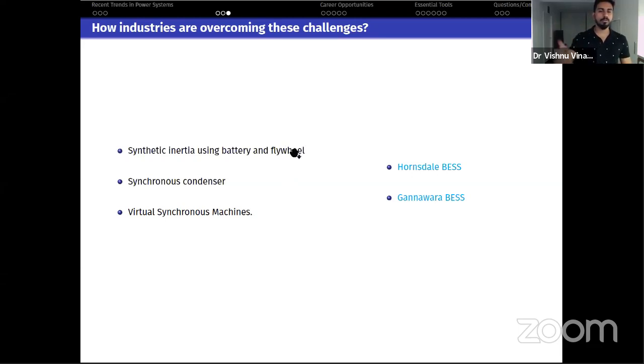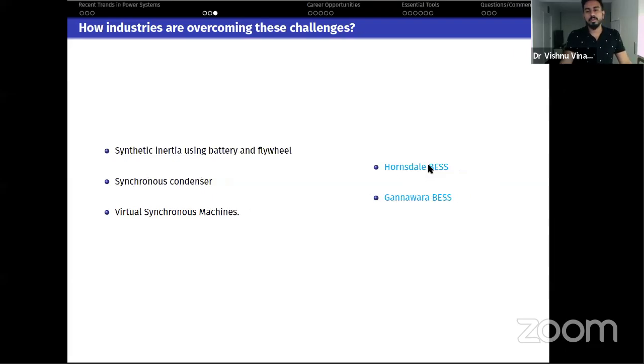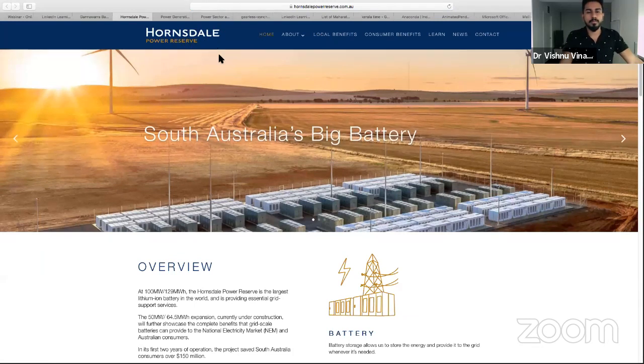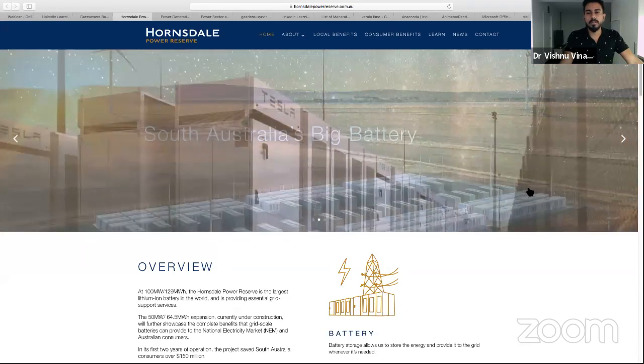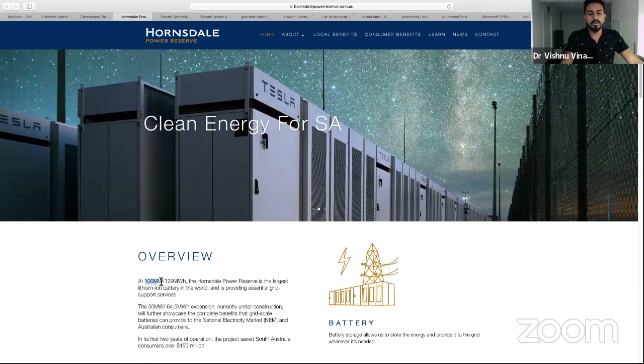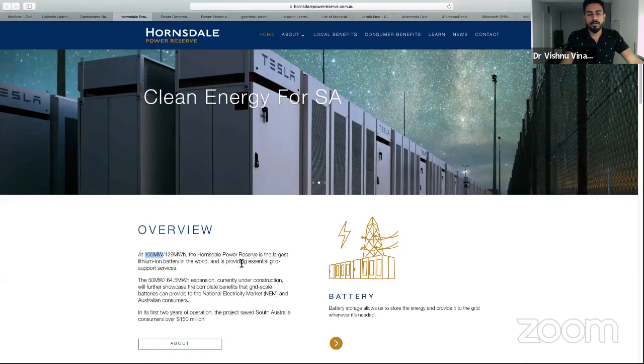Similarly, flywheels are huge rotating masses, so they store inertia and work in a similar fashion. Utility scale batteries are being installed in many power system networks, and I have provided an example here. This particular project is called the Hornsdale Battery Energy Storage System, in South Australia. You can see that these blocks are all batteries made by Tesla. These are Tesla battery packs, and the capacity of this battery is 100 megawatts, and it is used specifically for providing essential grid support service. That means it is not used for generation or any other activity.